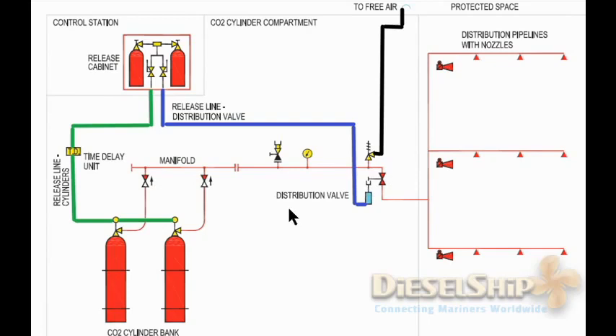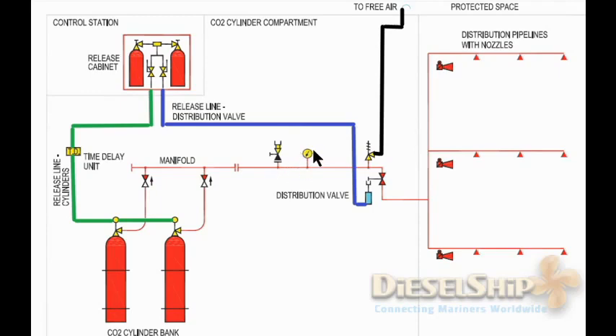On the main manifold, you must have a blank so that for maintenance purposes you can isolate the CO2 bottle section, blank it, and carry out maintenance. There is also a valve through which you can connect air — either from the engine room or from shore, depending on whether you are in dry dock or not. On the manifold you also have a pressure gauge indicating whether the line is pressurized.